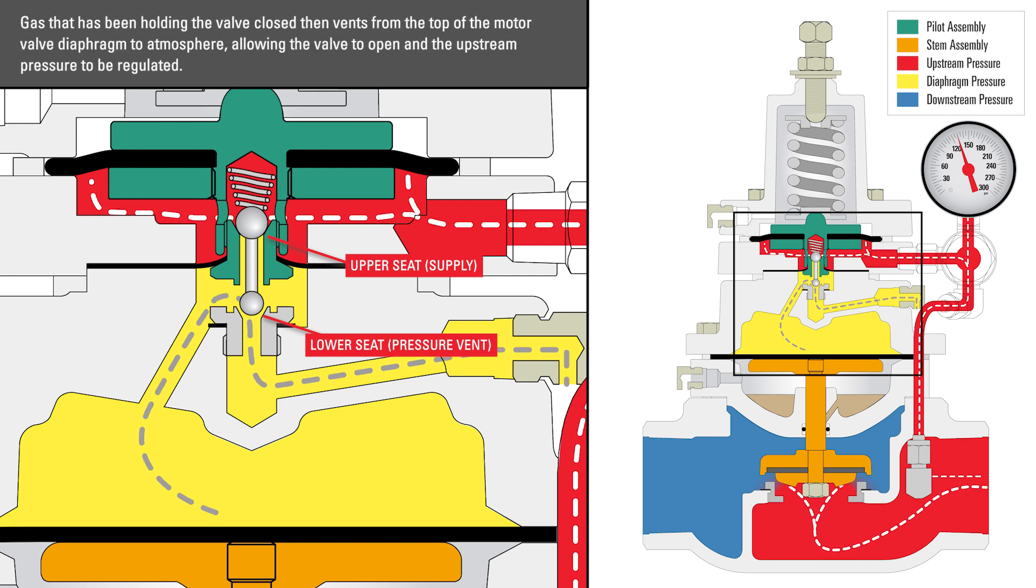Gas that has been holding the valve closed then vents from the top of the motor valve diaphragm to atmosphere, allowing the valve to open and the upstream pressure to be regulated.